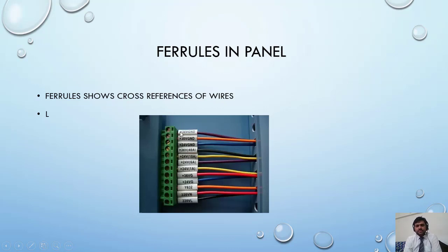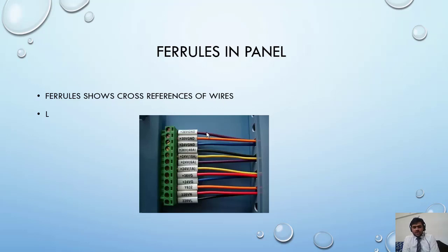If the ferule consists of information of both the local as well as the remote side — in other words, both the source and destination addresses are mentioned on the ferule — then it's called a cross ferule. It's always good to have a cross ferule, which is really useful for troubleshooting.